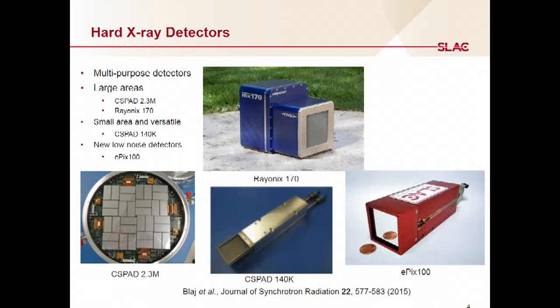It has single photon sensitivity, which means it can detect a single photon, as well as a reasonable dynamic range, which means it can detect several hundreds, maybe even thousands of photons, depending on the photon energy. There is the Rayonix, a scintillation detector, which can run at 30 hertz, but is also very good if you need really high dynamic range. So if you anticipate very strong signals, like very intense Bragg peaks, this is the detector that you would use for that.